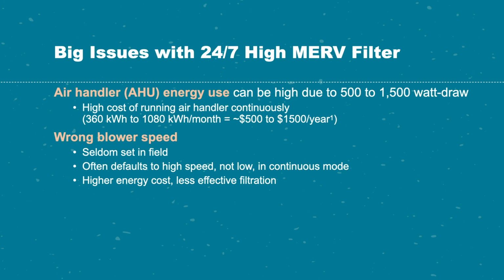HVAC contractors don't go in and check and then change the continuous speed to low, which it should be. If you're running continuously, you want it in the lowest possible speed. So part of this high cost is because it's running on the highest flow rate possible. And that's not the best for filtration. The best filtration is a much lower airflow rate because you're dropping more of your small particles.